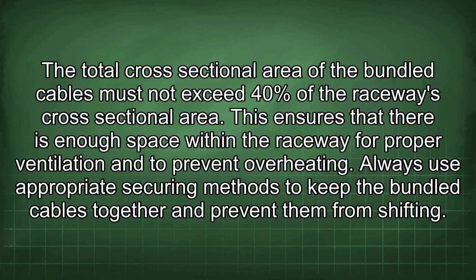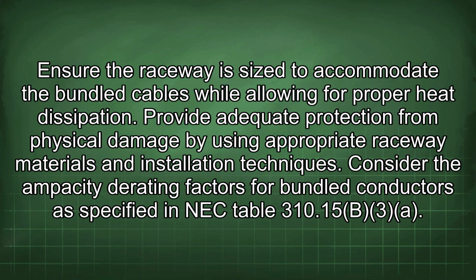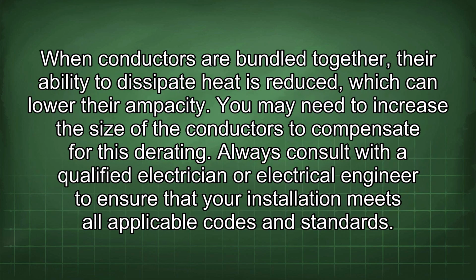Always use appropriate securing methods to keep the bundled cables together and prevent them from shifting. Ensure the raceway is sized to accommodate the bundled cables while allowing for proper heat dissipation. Provide adequate protection from physical damage by using appropriate raceway materials and installation techniques. Consider the ampacity-derating factors for bundled conductors as specified in NEC Table 310.15b3. When conductors are bundled together, their ability to dissipate heat is reduced, which can lower their ampacity. You may need to increase the size of the conductors to compensate for this derating.